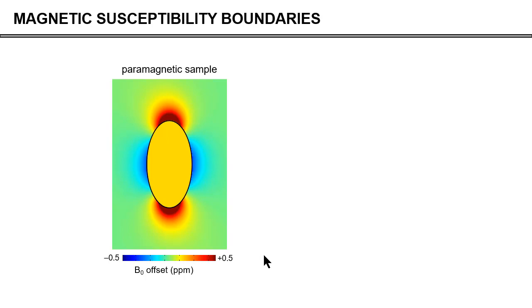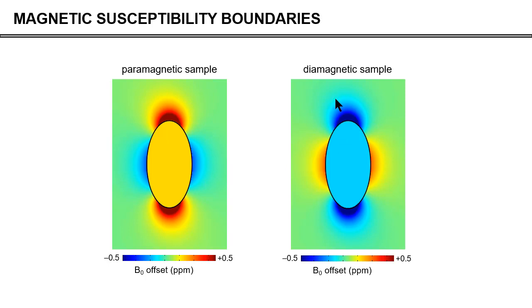Most of the time we just show the amplitude of the magnetic field. In this scenario with a paramagnetic sample, the magnetic field inside the sample is slightly higher than the applied B0 field, and because you have an interface, you're going to get inhomogeneity outside of this sample. If the sample were diamagnetic, it would be the same thing — inside the sample the magnetic field would be slightly lower than the applied magnetic field, but you would still get an inhomogeneity around that sample.